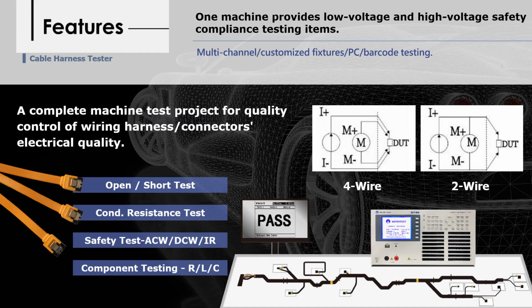The Microtest cable tester combines low voltage and high voltage testing items, including short circuit test, conduction impedance test, AC withstand voltage, DC withstand voltage, insulation impedance test, and component characteristic test. For conduction impedance test, both 4-wire and 2-wire measurements are provided.